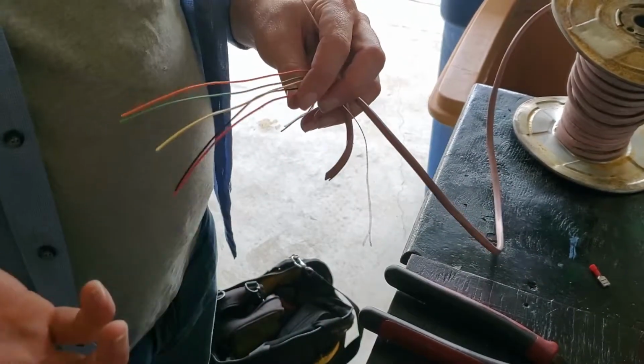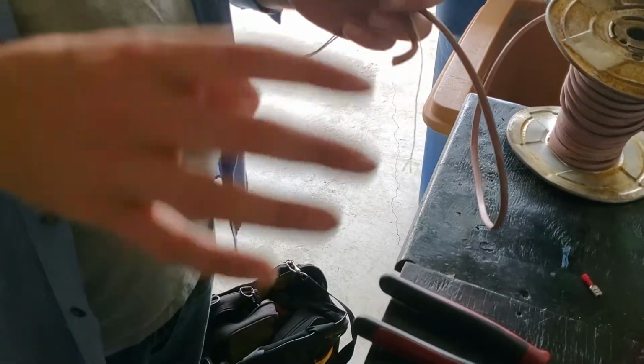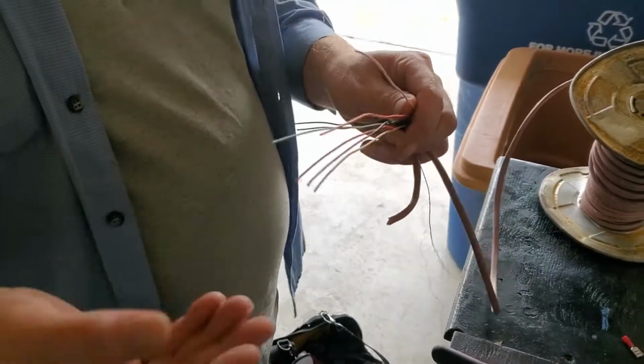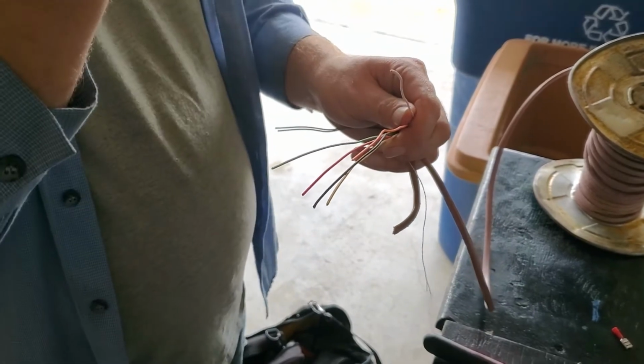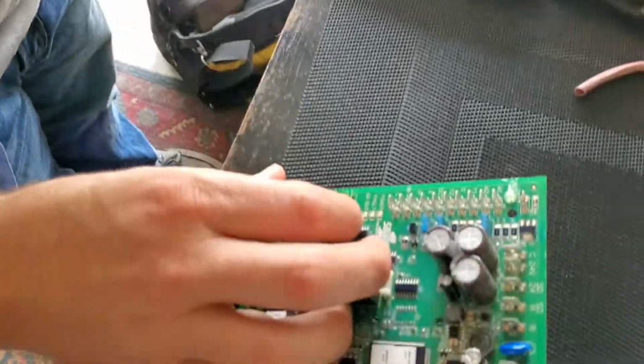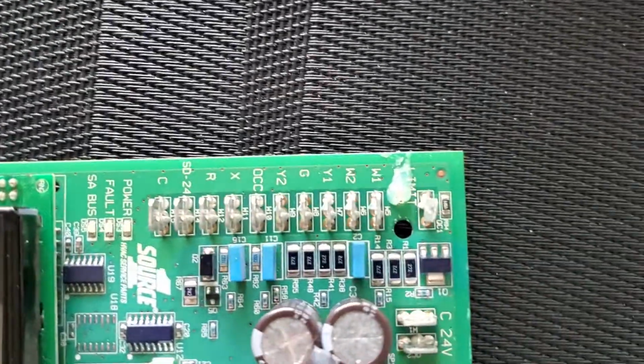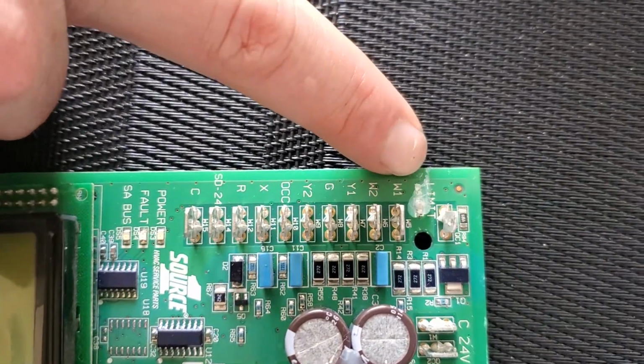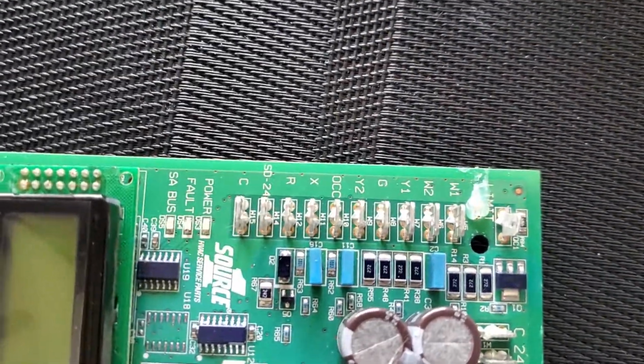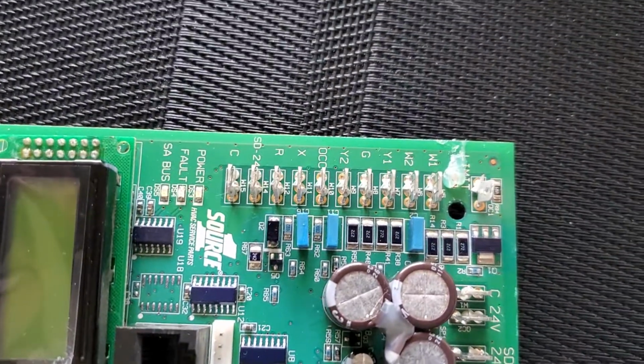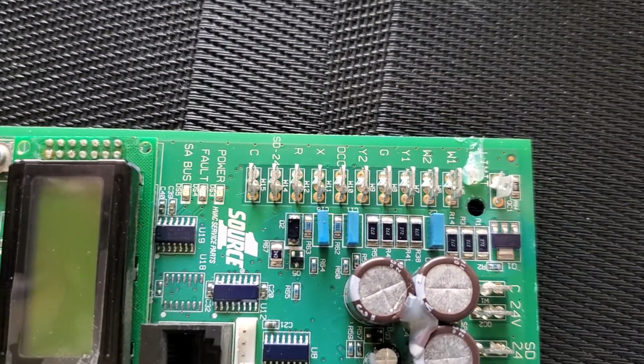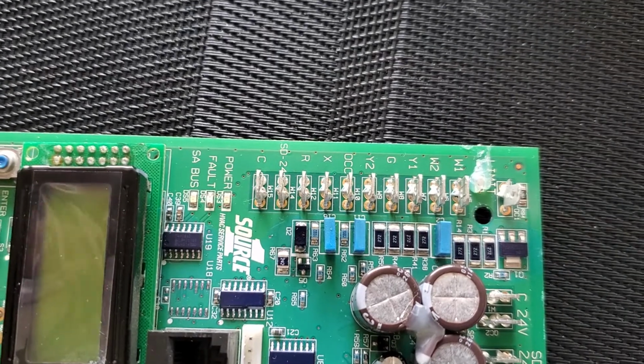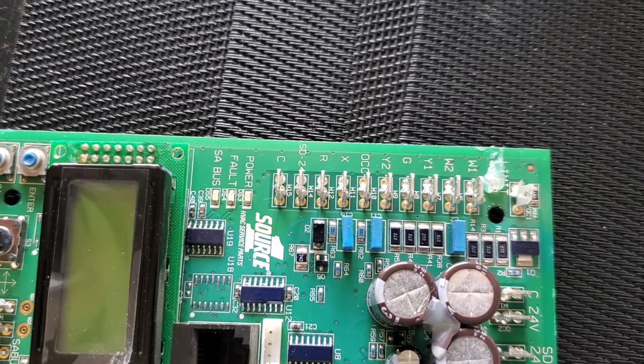That's something you have to pay attention to when you take the old thermostat off. You have to see what was hooked up, even though the colors aren't necessarily important since we're going to rewire it. Was it using OB? This one doesn't have it, but where it says W1, it would say W1/OB, and give you an emergency heat option. So for W1 or OB on a heat pump, you'd use orange. For emergency heat, you'd use white.